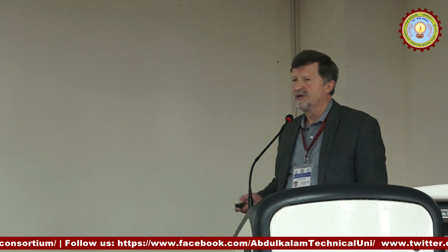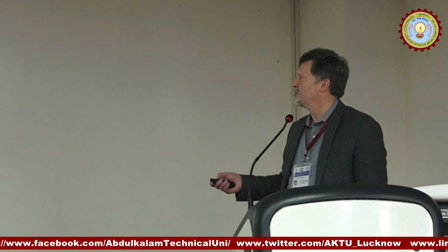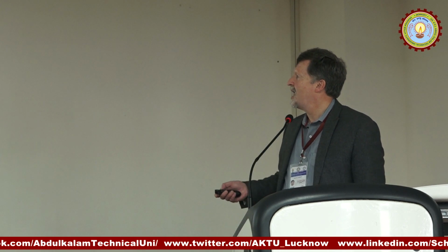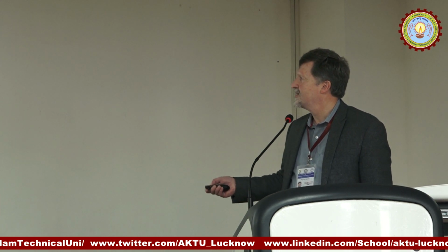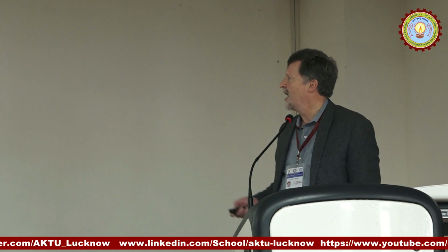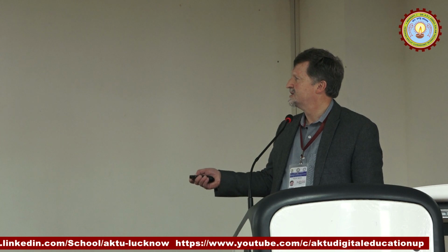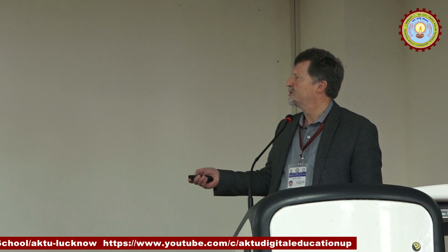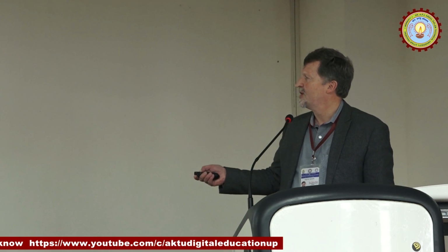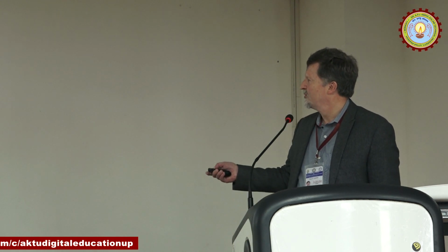And so we've moved to using an inverse Z chirp transform to carry out this process. And that allows us to sample much more finely in the time domain than we can with the inverse Fourier transform, and has certainly improved our results as shown in this set of slides. This would be typically the results. You can see the temporal component, which is associated with penetration into the breast, is somewhat crude, whereas with the inverse Z chirp transform, we get a much smoother and higher resolution image.